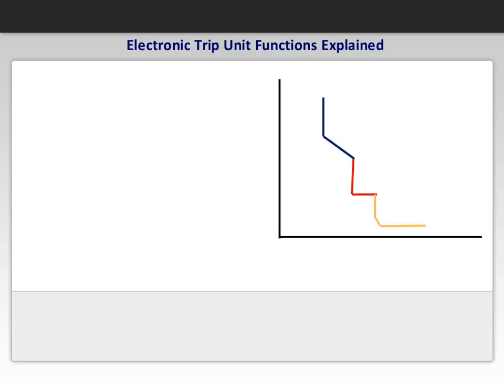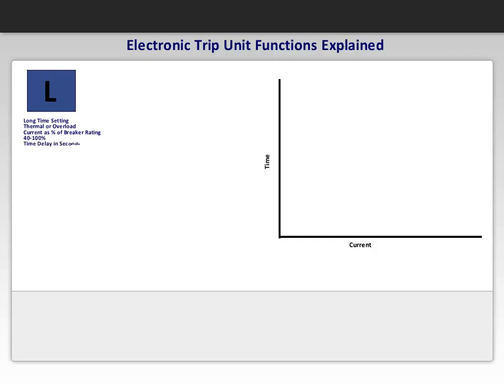Now that we've established what an electronic trip unit is, let's explain the settings that are available. Every breaker, when installed, has a trip curve based on time and current, as seen here. Let's go over how that curve gets its shape. You may have heard of the designations L, S, I, and G when selecting a trip unit for a breaker. We will start with the L first. It stands for long time setting. It allows for long time setting for the thermal portion of the trip curve and is set as a percentage of the breaker rating, usually 40 to 100%, and allows for a time delay setting in seconds.